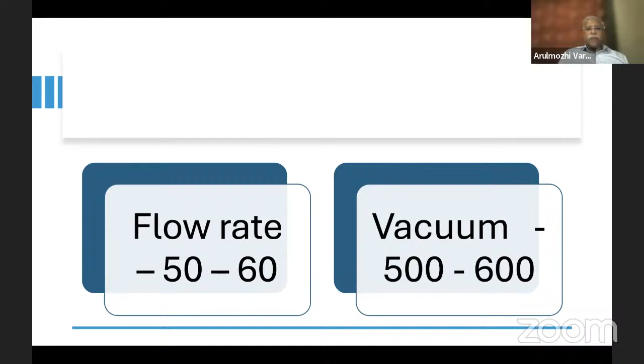So by this, setting your energy settings, your flow rate and vacuum on linear, all of these can be set on linear in most machines now, except very entry-level machines. Most mid-level and of course all high-end machines, you can set all the 3 at linear levels, which gives you enormous amount of ability to tailor it on a second-to-second basis by your own foot.